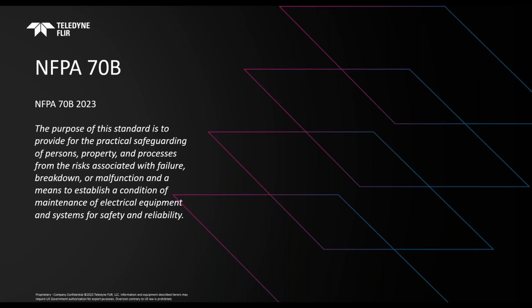With regards to NFPA-70B, I pulled this comment directly from the literature. The purpose of the standard is to provide for the practical safeguarding of persons, property, and processes, from the risks associated with failure, breakdown, or malfunction, and a means to establish a condition of maintenance of electrical equipment and systems for safety and reliability. So the language is slightly different from 70E in that we're talking about safeguarding of people, property, and process, really about the maintenance of electrical equipment and systems for safety and reliability. The two work in concert. 70B's focus is much more on the correct and effective maintenance practices around electrical inspections and maintenance.